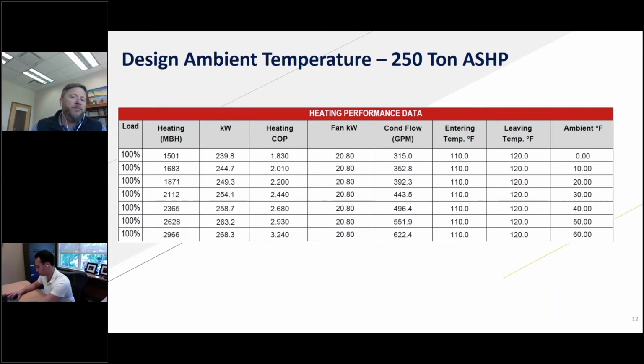With an air source heat pump, we're taking heat from outside. Even at very, very cold temperatures, there's heat that exists outside. We're taking it from outside and moving it into the building. Depending on what the ambient temperature is, if we think back to the refrigeration cycle schematic that I showed, the more lift we have to do, the less efficient we are, and the less work we can actually provide. What this chart shows is, if I'm going to stay at 120 degree hot water and look at varying ambient temperatures with the same equipment at full capacity, at a 0 degree ambient I'm providing about half of the capacity that I can provide at a 60 degree ambient.